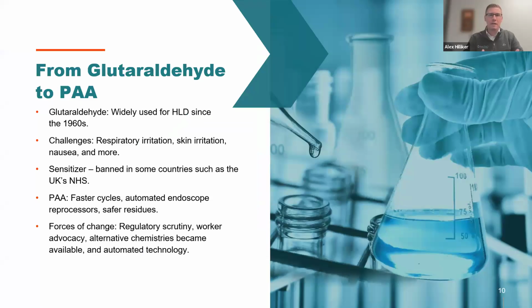On the high-level disinfection side, we share this because it's a very interesting and similar story to the evolution from ethylene oxide to hydrogen peroxide for HLD. So peracetic acid came about as the successor to a chemical called glutaraldehyde, which some of you may or may not still be using at your facilities. For those of you that may not be familiar, glutaraldehyde was the primary choice for high-level disinfection in hospitals since about the 1960s. It's a cold soak high-level disinfectant that also has a sterility claim if you let the device soak long enough. The problem is that glutaraldehyde vapors are toxic, and they can cause respiratory irritation, nausea, headaches, irritation to the skin if you're exposed, as well as a host of other health impacts.